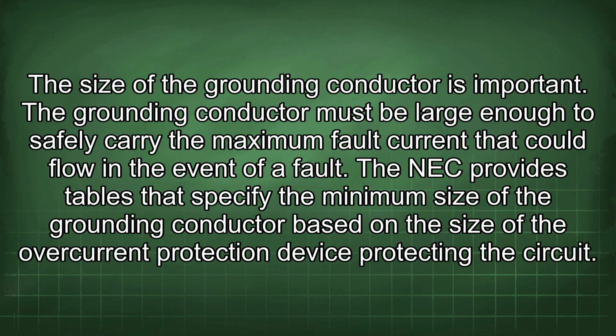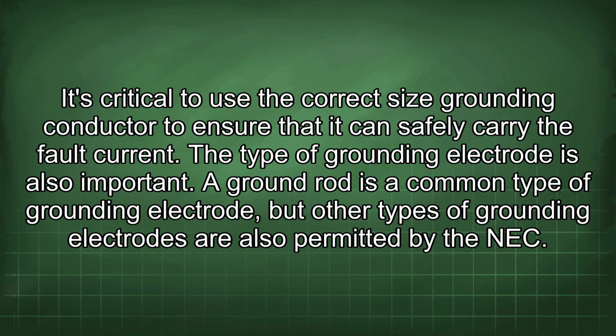The size of the grounding conductor is important. The grounding conductor must be large enough to safely carry the maximum fault current that could flow in the event of a fault. The NEC provides tables that specify the minimum size of the grounding conductor based on the size of the overcurrent protection device protecting the circuit. It's critical to use the correct size grounding conductor to ensure that it can safely carry the fault current.